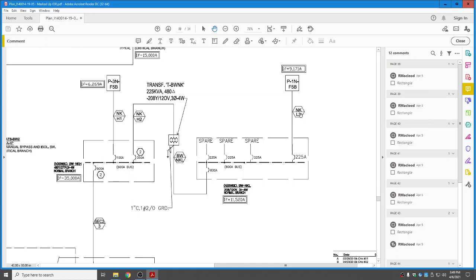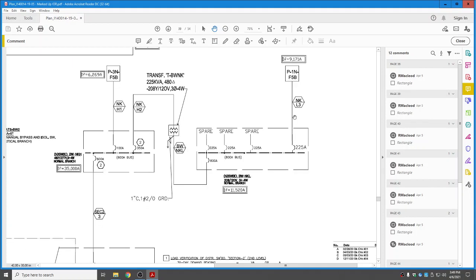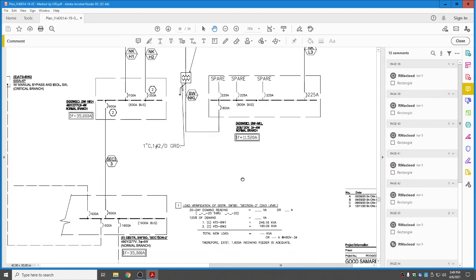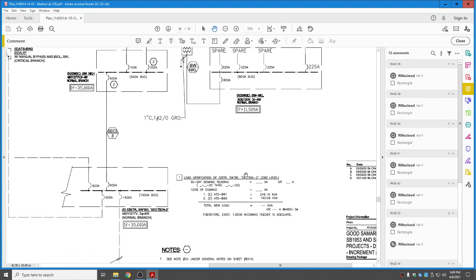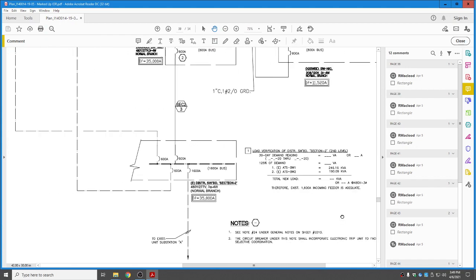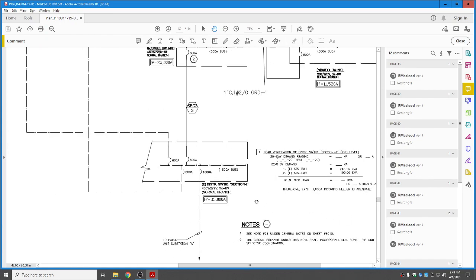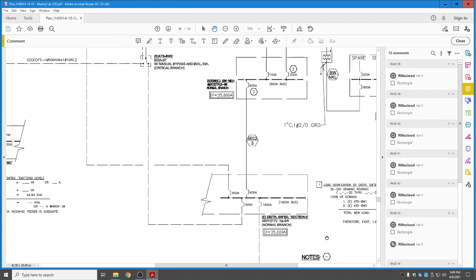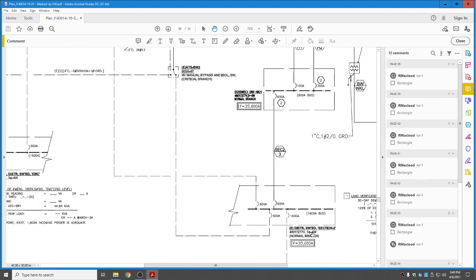The NKL3 tells us our conduit size and our feeder size going from this bucket or breaker up to our panel board. So that's the normal power system of our single line diagram. Now let's jump over to, from this single line diagram, we have normal power going in and being distributed to a couple of different levels here.